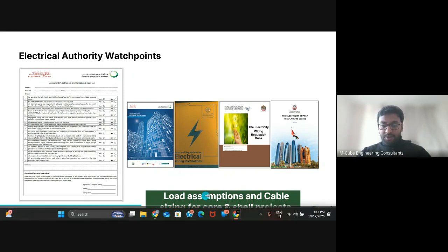Another important point I wanted to highlight was related to the electrical loads which are generally mentioned for core and shell. Generally, when you have core and shell, engineers assume loads which are very low because they don't want the electrical load to be very high at the initial design stage. But later on, when the design has been approved and moves to the construction stage, the contractors face a lot of challenges in terms of having proper loads for the core and shell area.